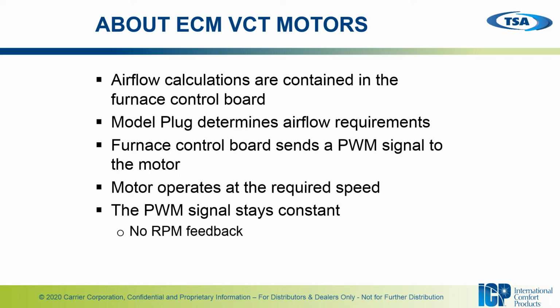Okay, so on the VCT motor, or the variable constant torque motor, like we said before, the airflow calculations are predetermined and programmed in the control board based on the model plug that's installed on the control board and the dip switch settings. Then the motor functions to speed based on those settings and programs.